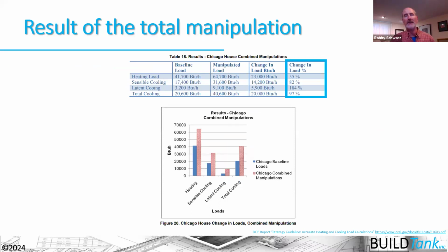And remember, as HVAC contractors are adjusting to building more modern, airtight, better building thermal envelopes, they're coming from a situation where they often wanted oversized equipment because it reduced callbacks ultimately. But in our modern day houses, that oversized equipment is not only energy inefficient, but it's also causing problems with the actual functionality of the equipment, which is causing callbacks and problems for HVAC contractors. So ultimately, we want systems that are right-sized for that particular house. And here, these are kind of techniques for understanding how we're going to get that right-sized equipment there.